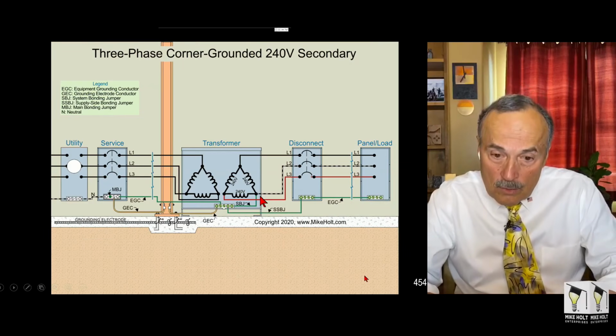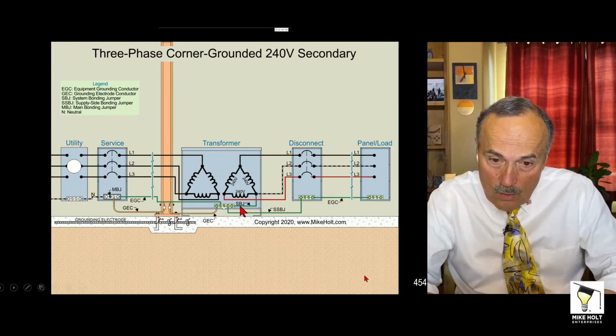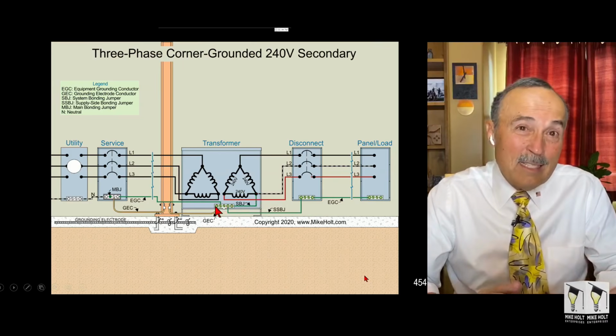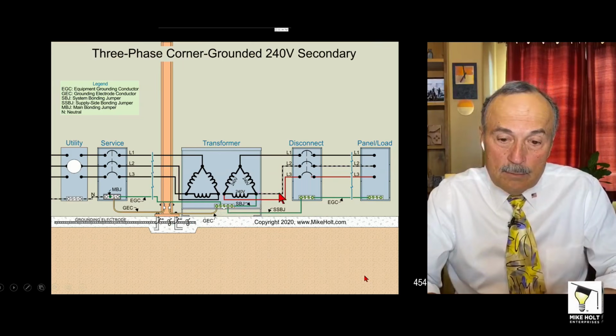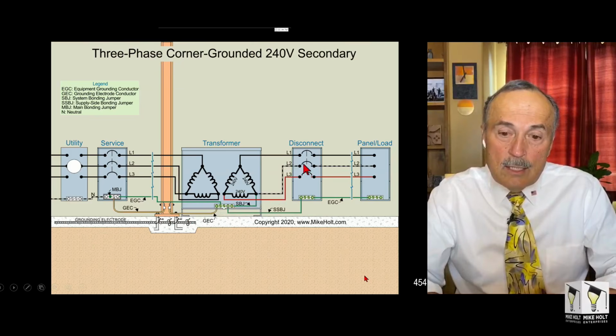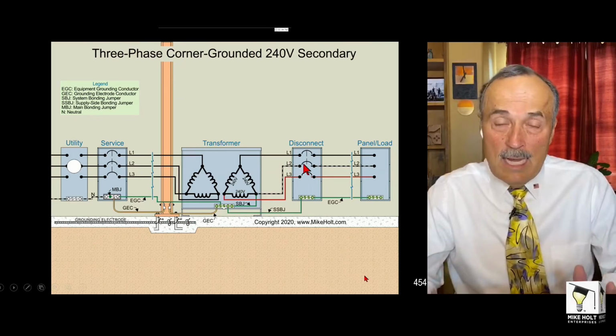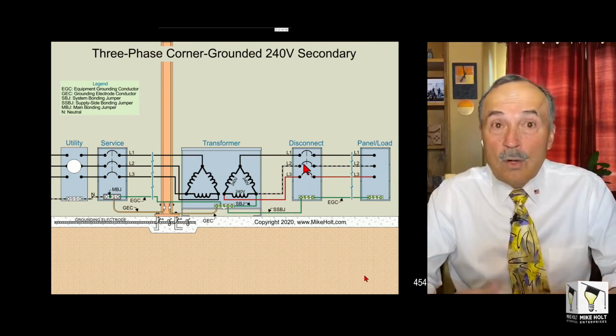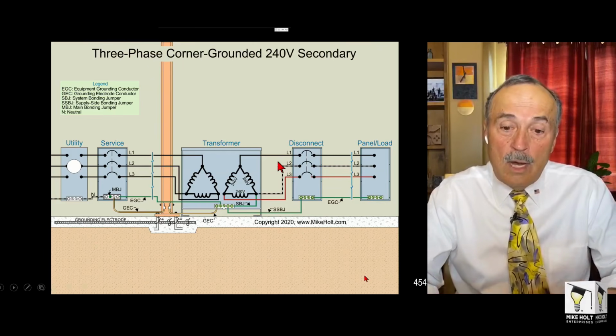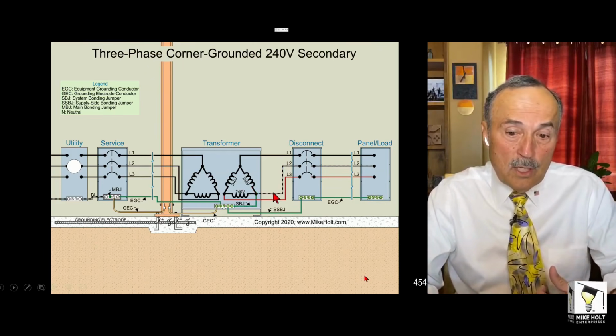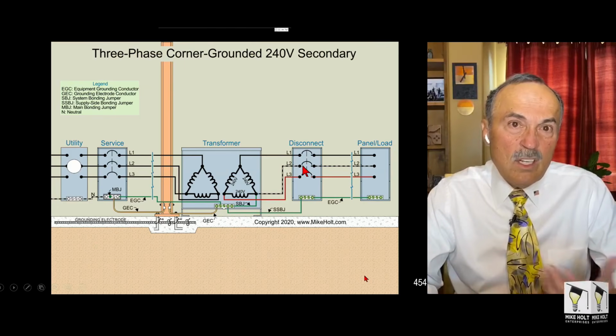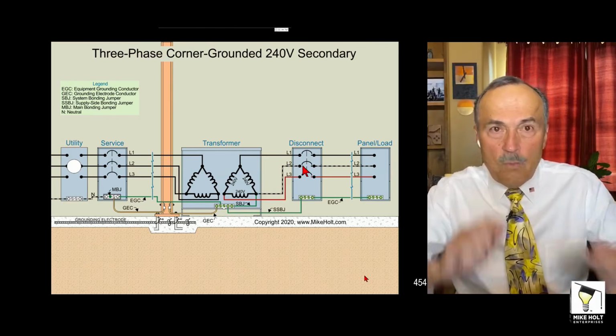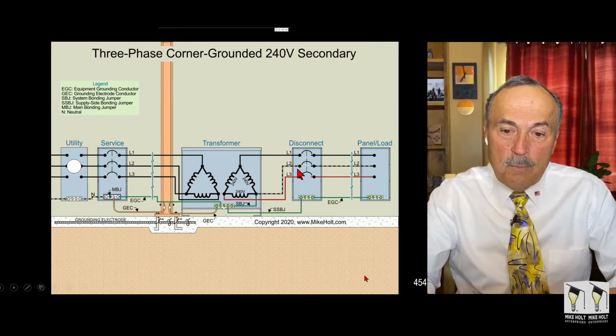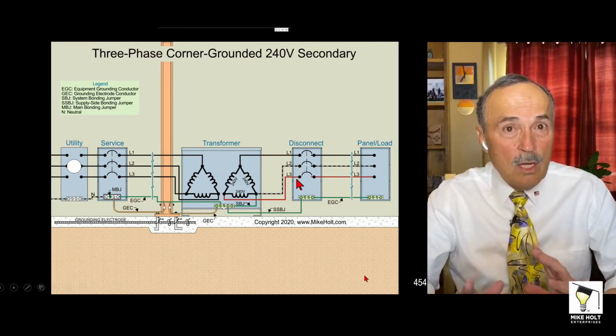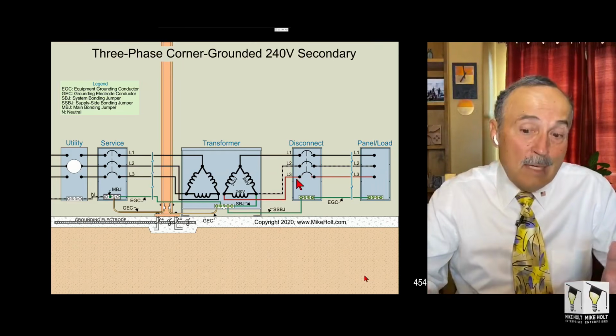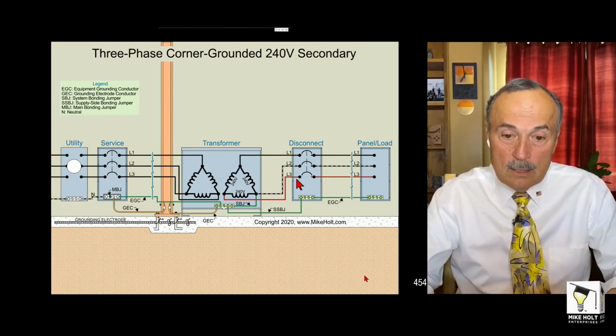The grounded conductor, which is right here. This is that corner grounded right here. Actually, it's bonded, and then we ground the equipment, but whatever. That's your grounded conductor. I think the practice is line 2, but it could be line 1 or line 3. It doesn't really matter. So I'm going to say it's line 2 in my example. So therefore, this is going to be a white wire or a gray wire, whatever you want it to be there, or black wire with white tape or whatever it is. That's black, white, red. Again, there's no color coding required by the code, but that might be a common system. All right, got the corner grounded system.